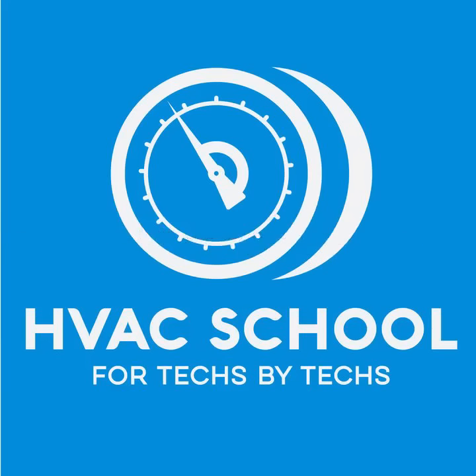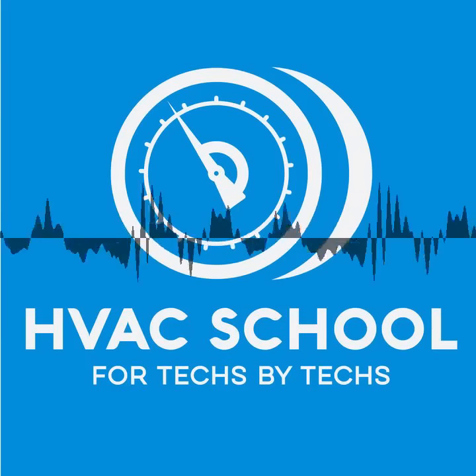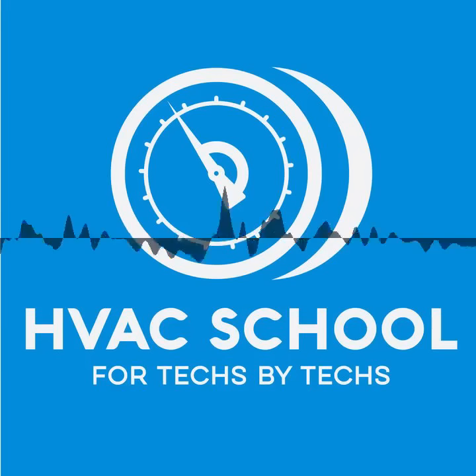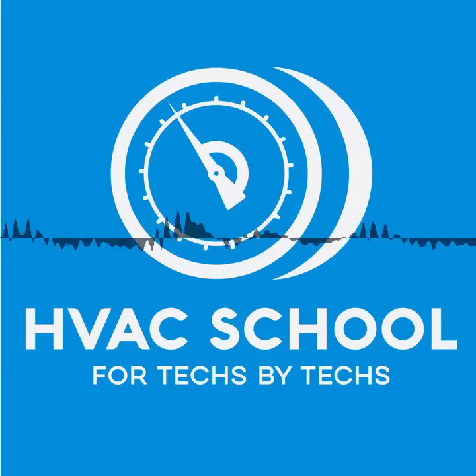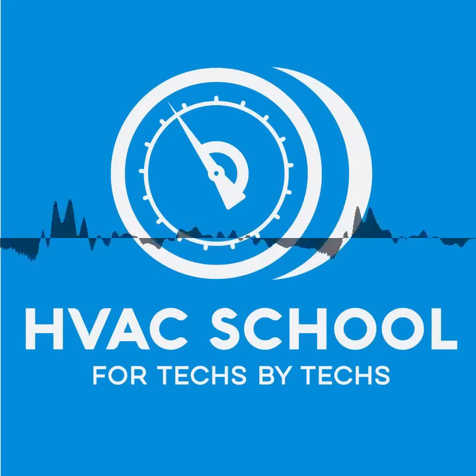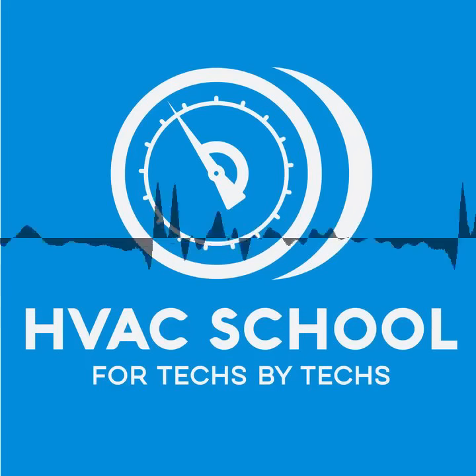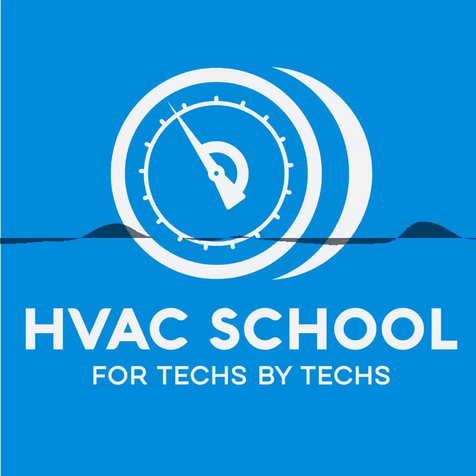So yeah. I shouldn't have said that because now that's kind of confusing because you have higher air velocity, which is going to impact your dwell time on the coil. But then if you're dehumidifying more air, then... So in a VAV application, you're going to reference static pressure to control the fan speed across the coil. So you're going to have a sensor, and the sensor is going to try to maintain a fixed static pressure. Usually 1.5 in the supply duct is the common target.